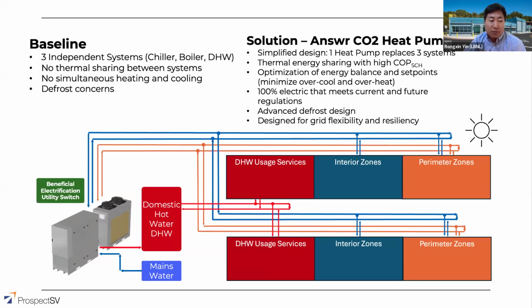In addition to the end performance testing at FlexLab, we also observed the unique design of the gas cooler system, which has an advanced defrost design, and the heat pump has a built-in controller capable of grid interactive control, for load flexibility testing as well as grid resilience, along with an energy storage component. You can see the diagram here.